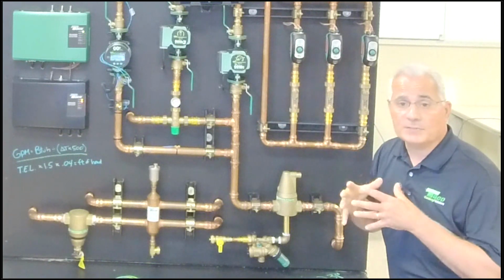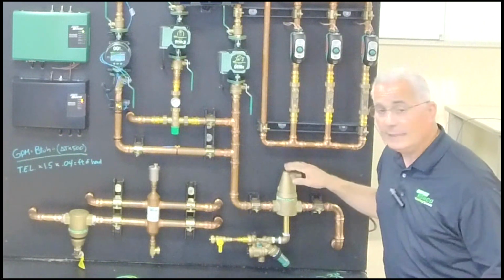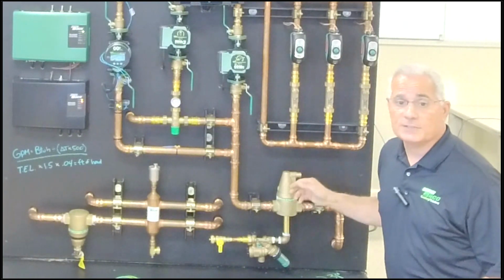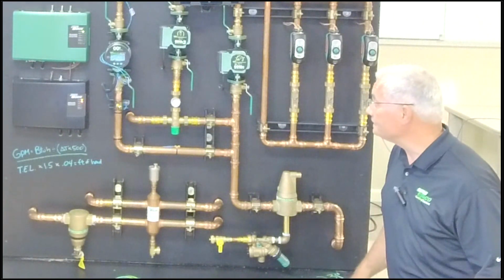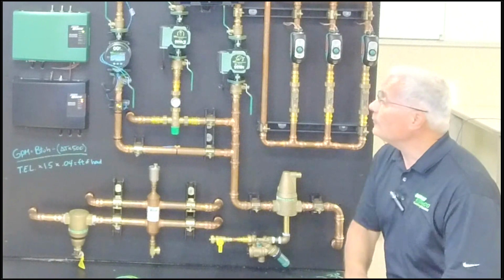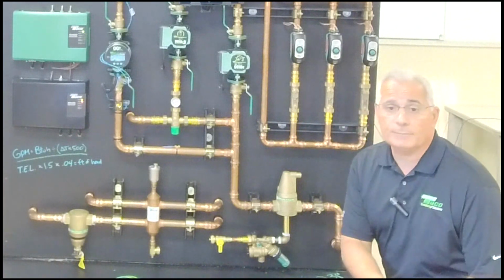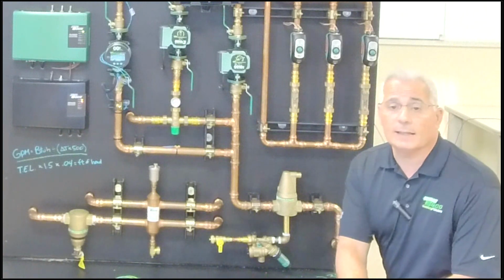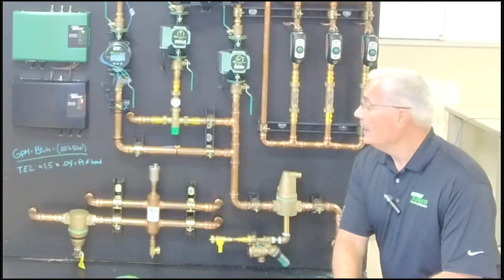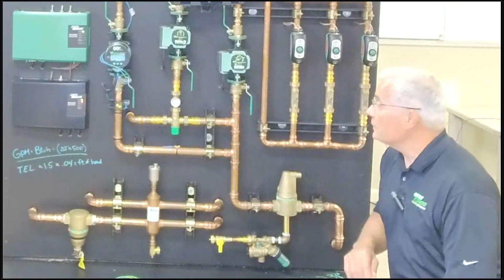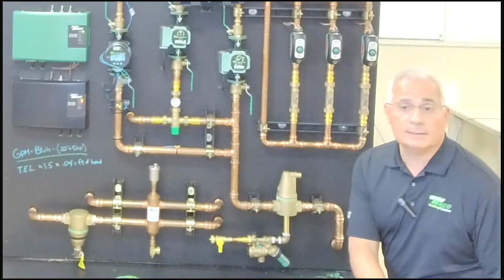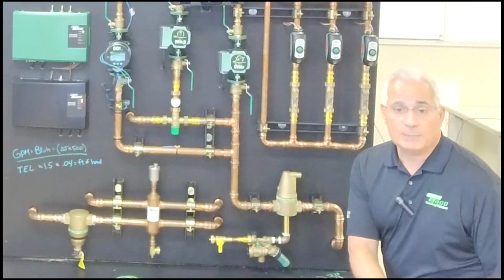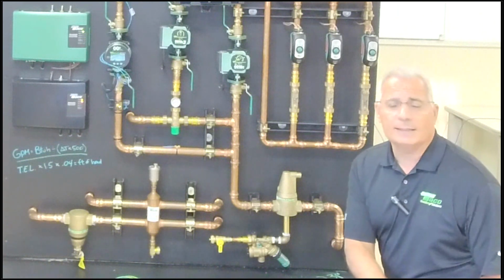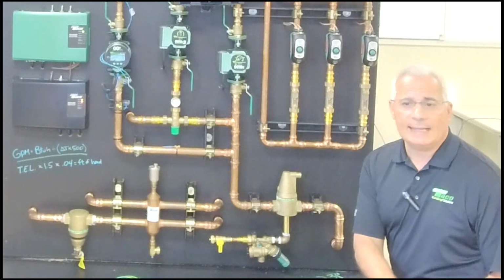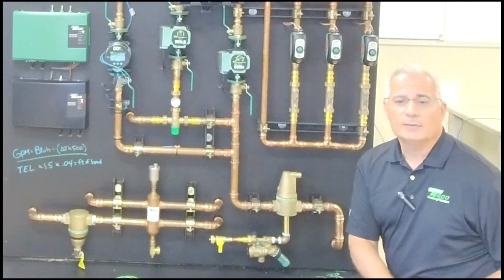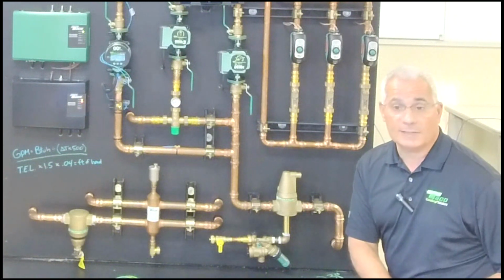That means my air bubbles in solution get squeezed down and easily dispersed from the system from our 4900 air separator. Now, if you recall from previous webinars when we talked about pipe sizing, and this is in the TACO catalog, I believe on page 57, this is 1-inch pipe. So the potential on the 20-degree delta T system is 8 GPM. I know the TACO catalog says 9. We're more comfortable saying 8 because that's going to make sure that we're staying within 4 feet per second so we don't create any velocity noise.